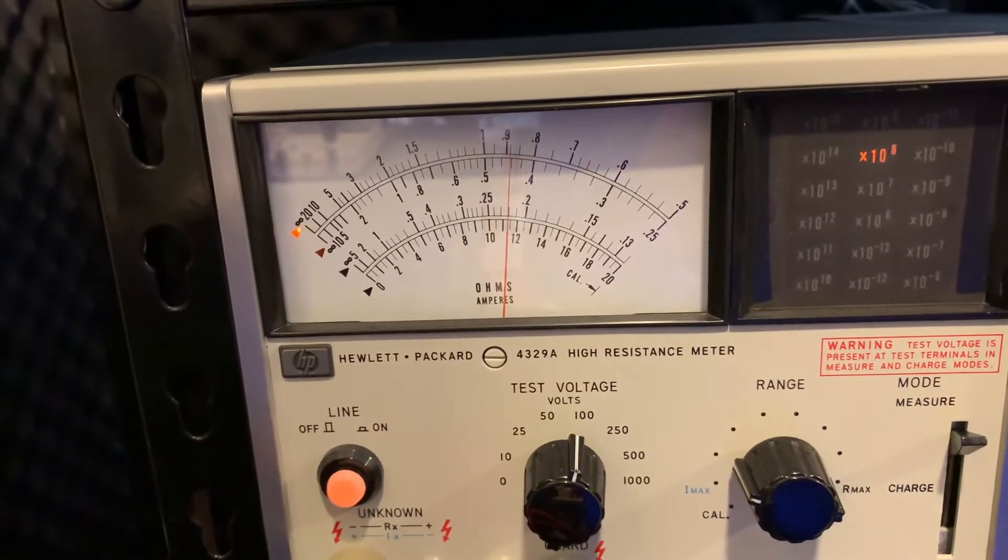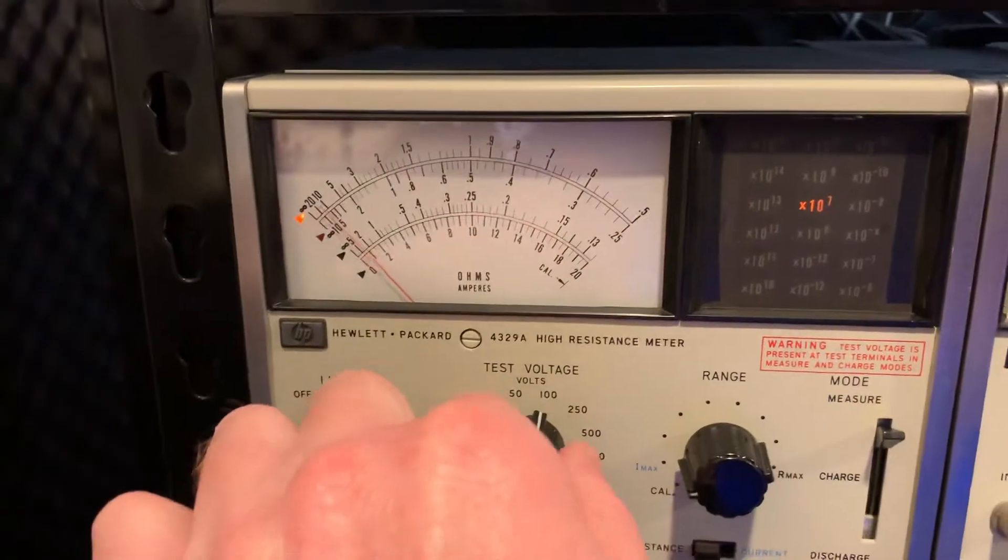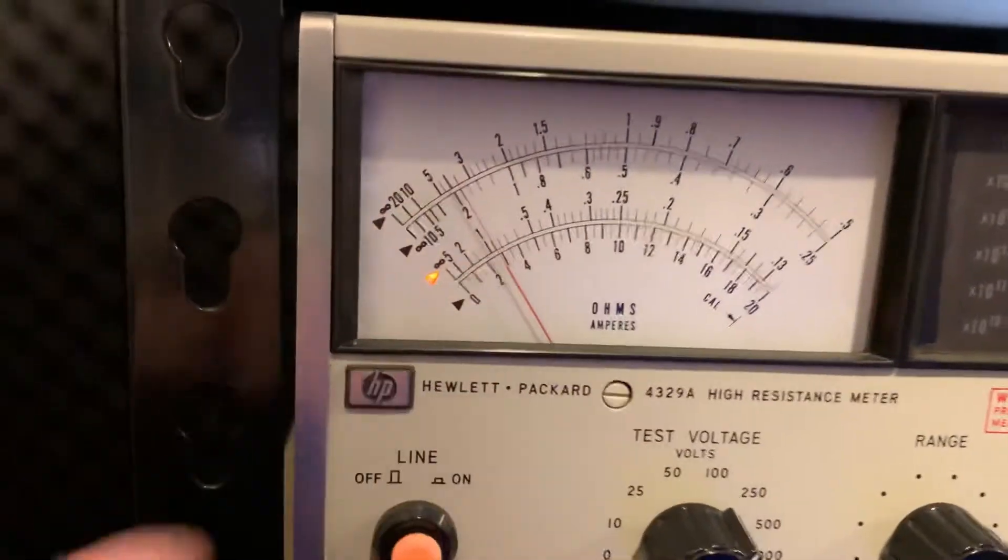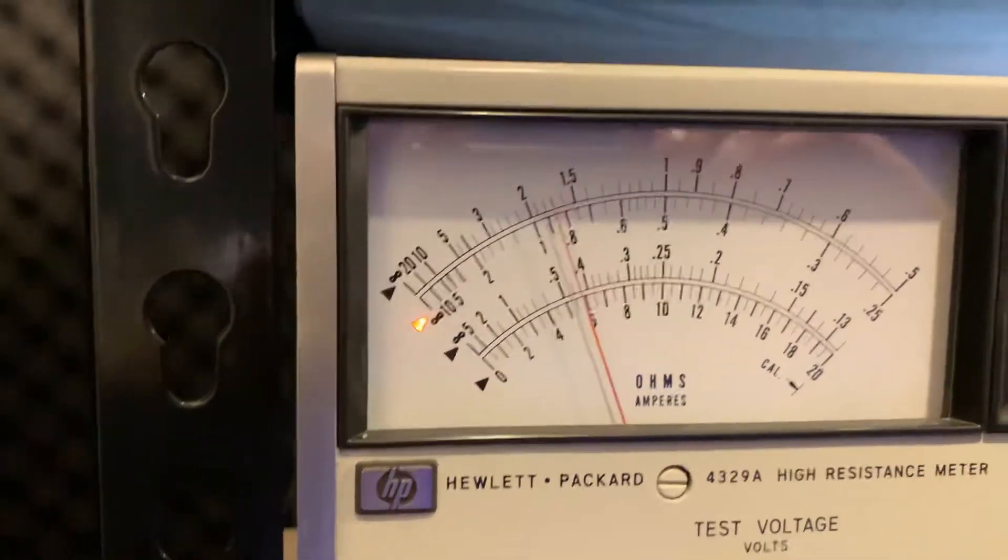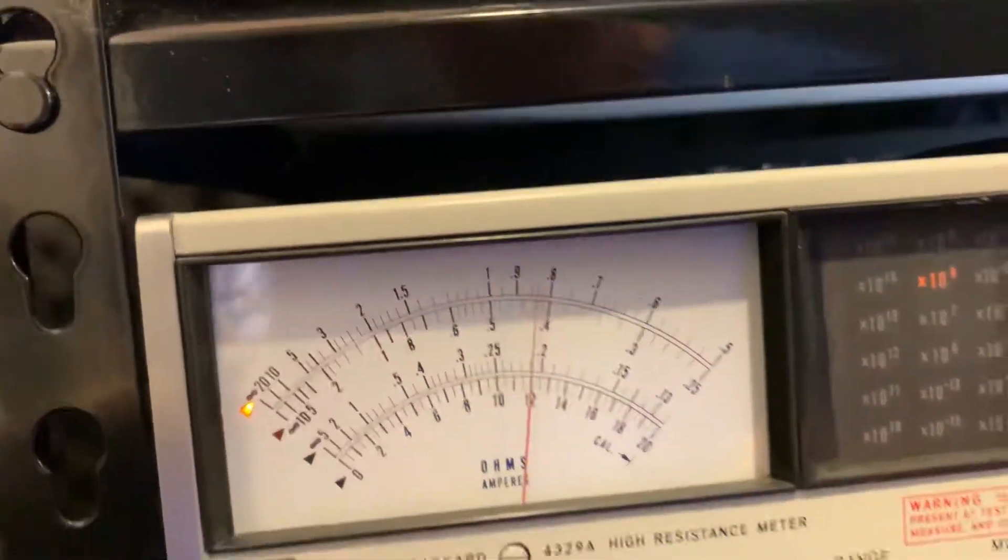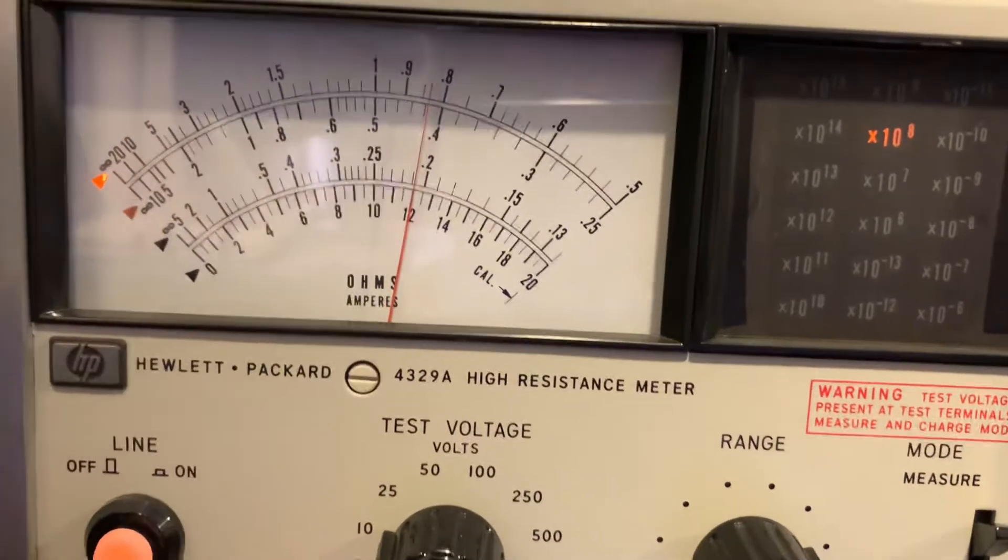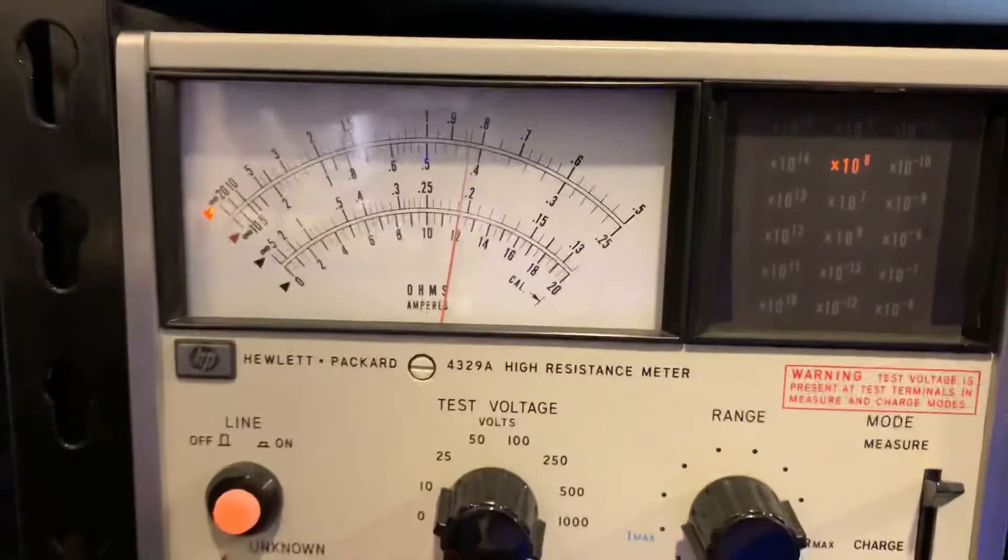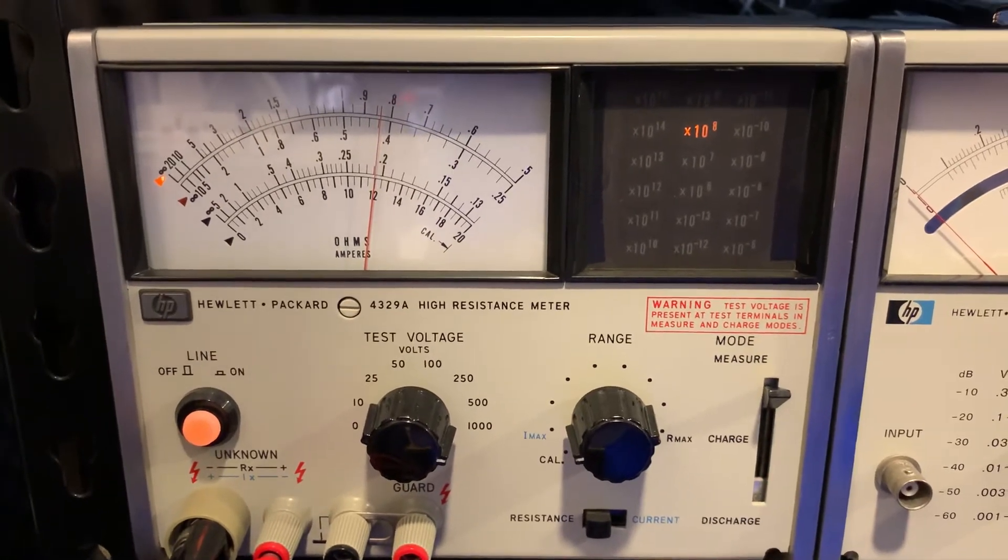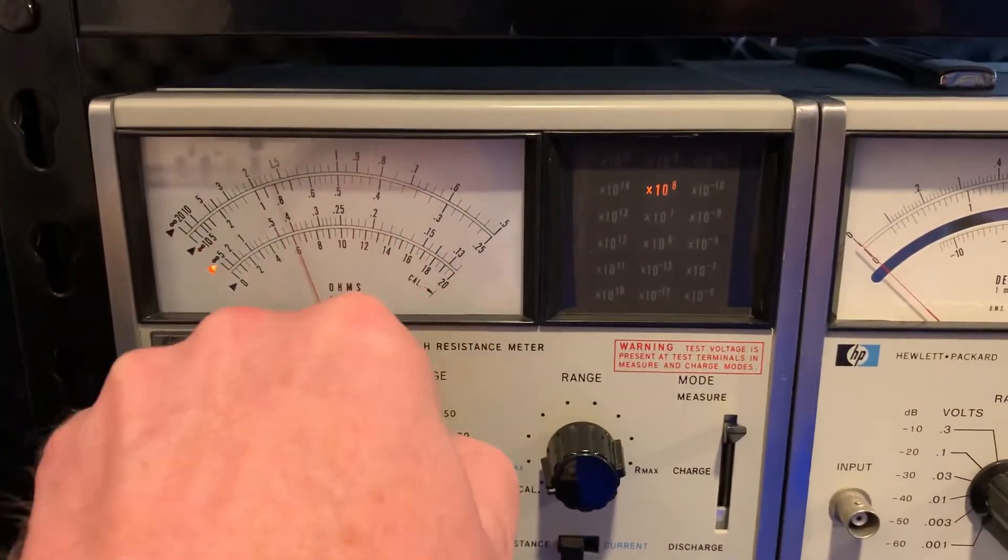That's correct, and that's on the 100 volt scale. 250 volt scale, just below 0.9. On 500 volts, just below 0.9. And on 1000 volts we're seeing a slight difference, a little bit above 0.8 but below 0.85. It's not uncommon for resistors to show slightly different resistance values based on voltage. We're going to back this off, discharge.